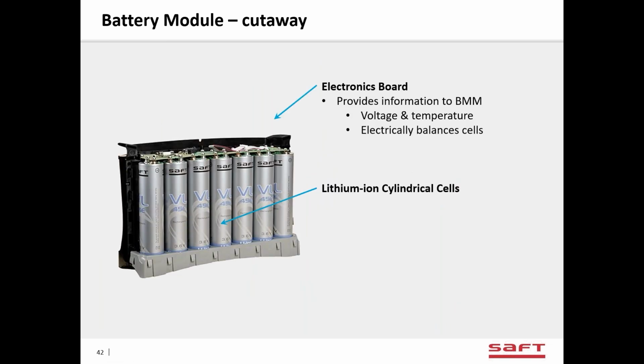This is a look at how the battery module looks inside. Each module has 14 cells. For the 120 volt market, we use what we call a 23 volt module, and there's 7 cells in series and 2 cells in parallel inside that module. So we can change that circuit board at the top, that is the bus bar. And for our 46 volt modules, all 14 cells are in series.